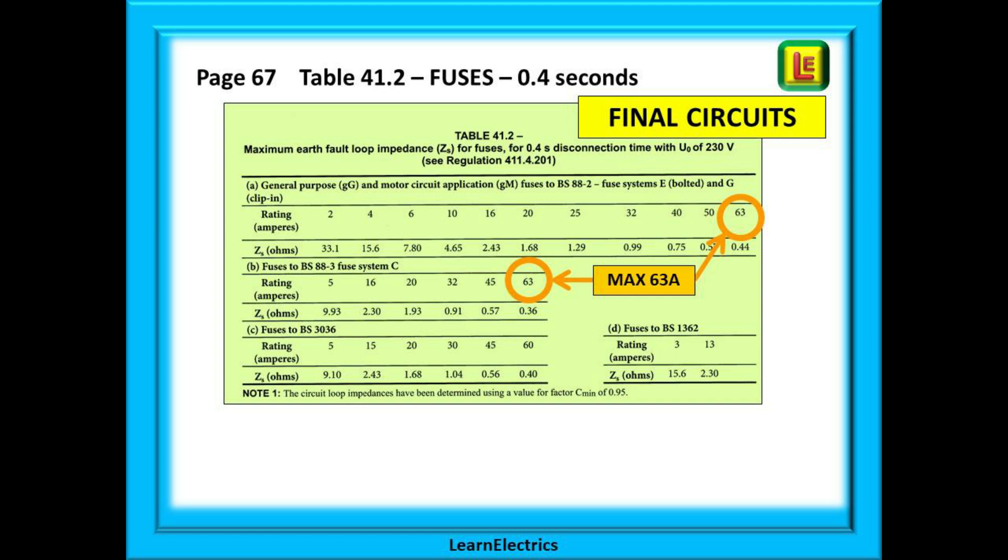This table is for final circuits only. The next fuse type is BS3036, the old re-wireable type fuses. And lastly, the plug-top fuse BS1362. Look also at Note 1 just below the table. It states that these tables have been adjusted for a CMIN factor of 0.95. This is an adjustment that has already been made to the ZS figures to allow for 5% voltage fluctuations. And we cover this in more detail in another video. You may get a question that asks what the CMIN factor is. And now you know. 0.95.